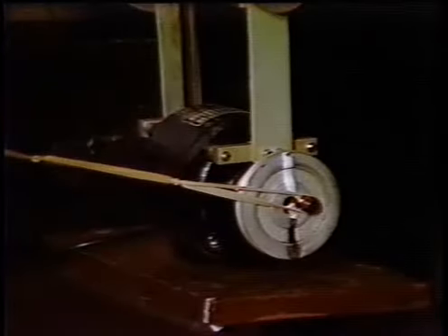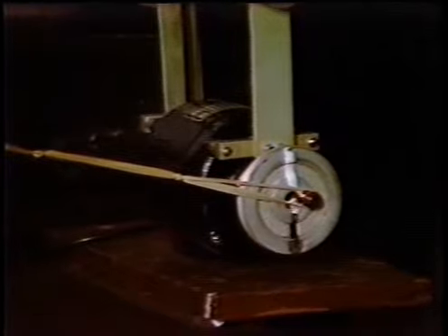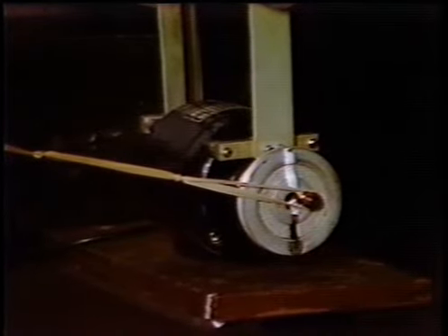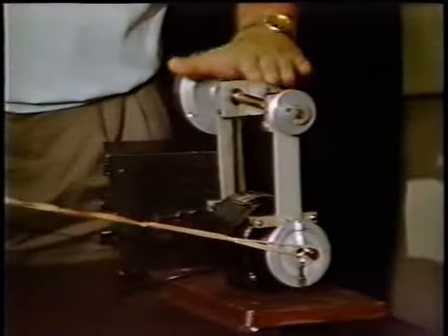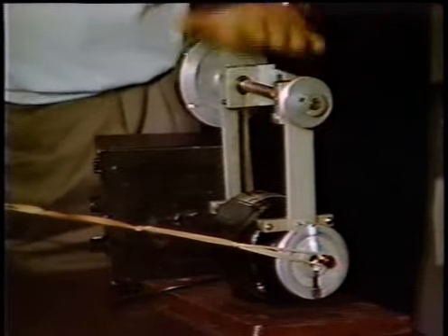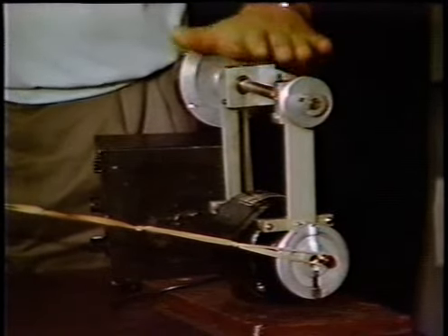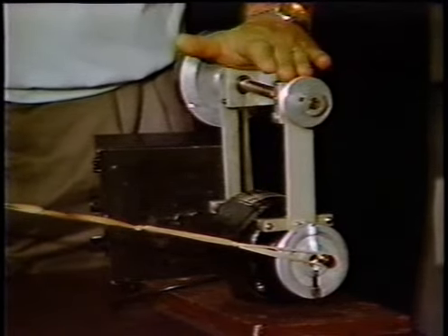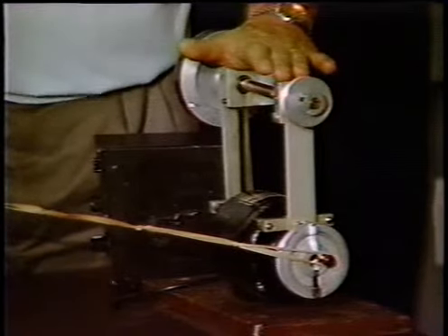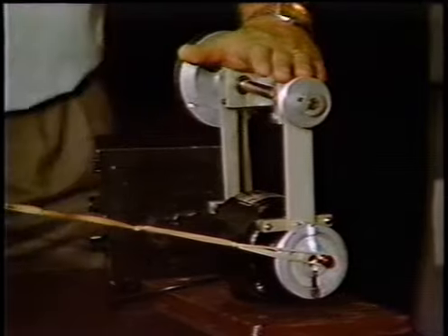As we mentioned, one of the reasons that resonance is such a very, very common problem is that every element of a machine or machine system, including the base, the foundation, the bearings, the piping, and so forth, has different degrees of mass and stiffness, hence different natural frequencies. However, you can take any individual element of a system and it will have not just one natural frequency, it'll actually have essentially an infinite number of possible natural frequencies. And that's what we want to show you here with this very simple demonstration.